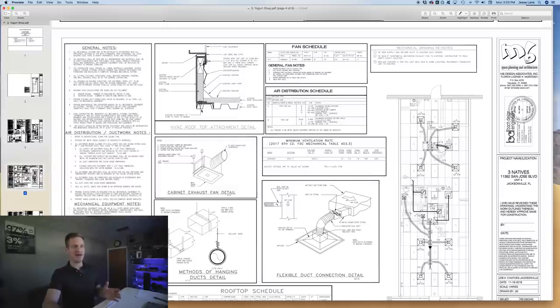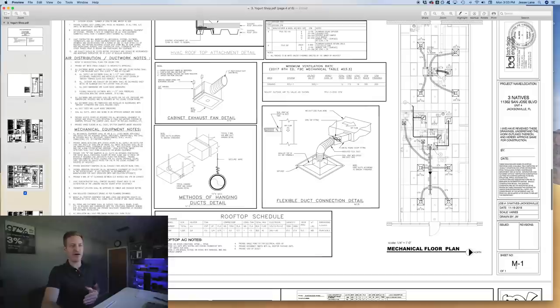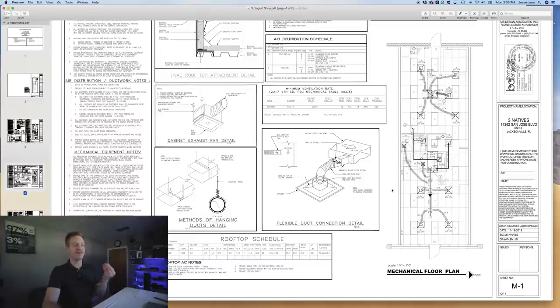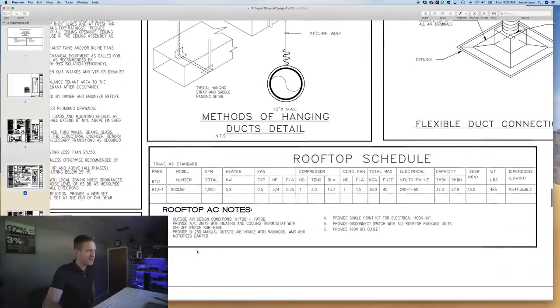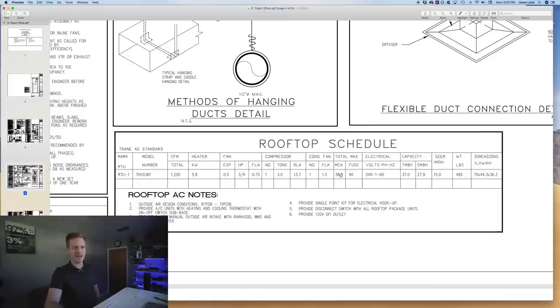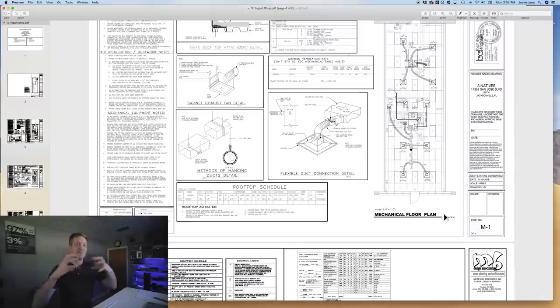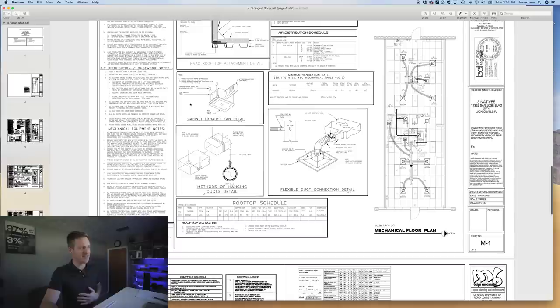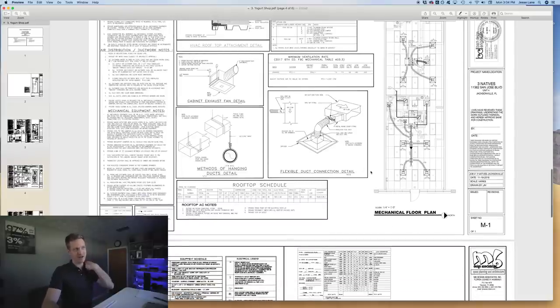There's a HVAC rooftop detail showing how the RTUs — rooftop units — attach and bolt to the roof. The mechanical floor plan shows main duct trunks with branches of flex duct above the ACT. The RTU schedule lists each unit: RTU1 shows the CFM, fan horsepower, compressor, condenser fan, and electrical requirements — such as 240-volt single phase — so your electrician and mechanical contractor can coordinate and make everything fit together.